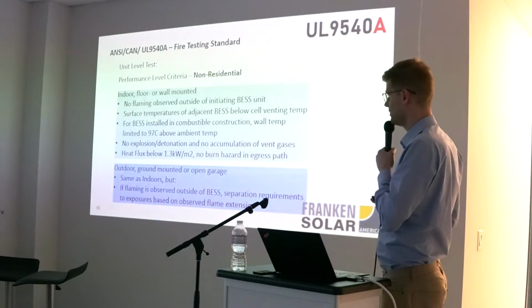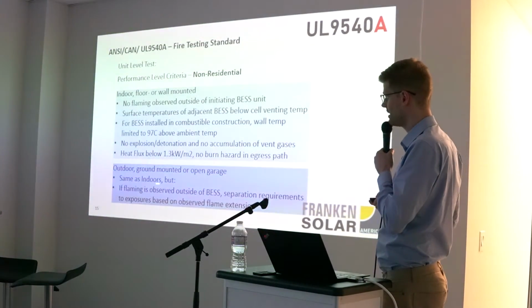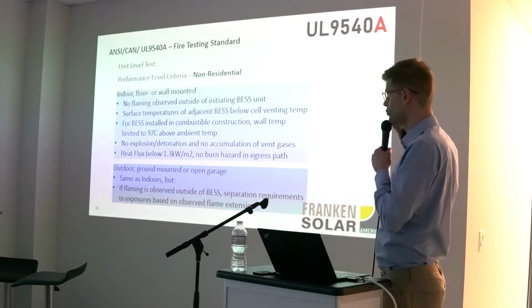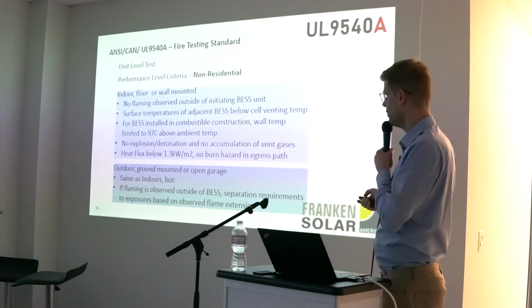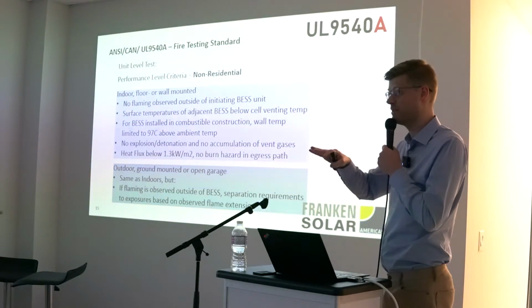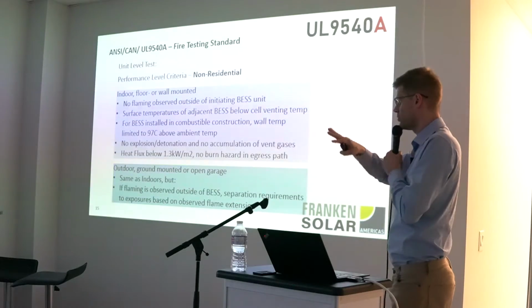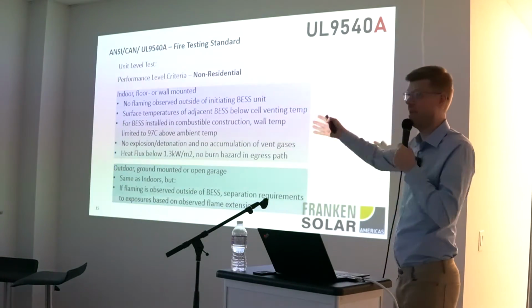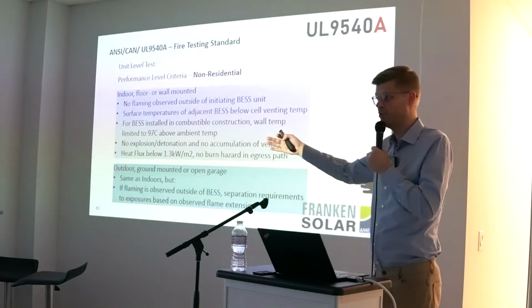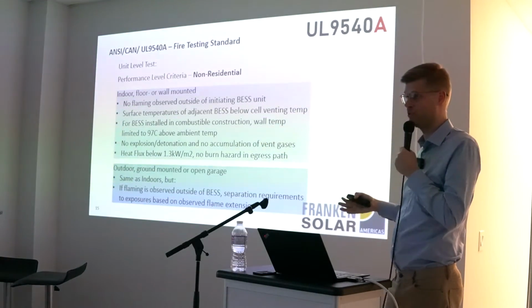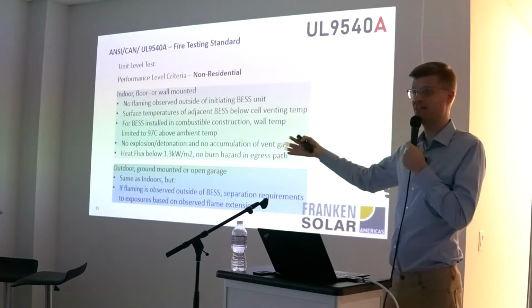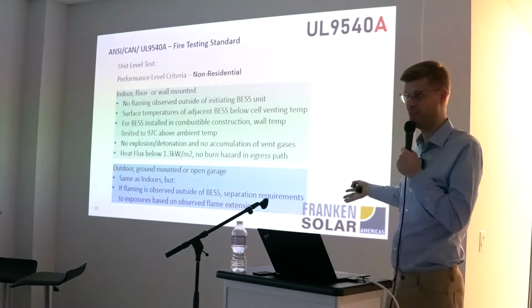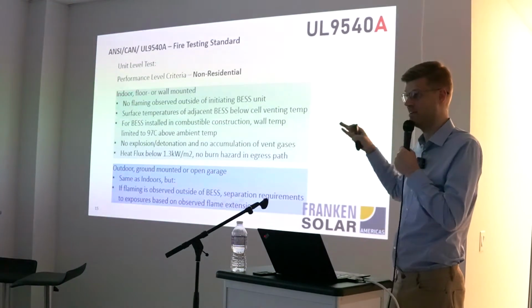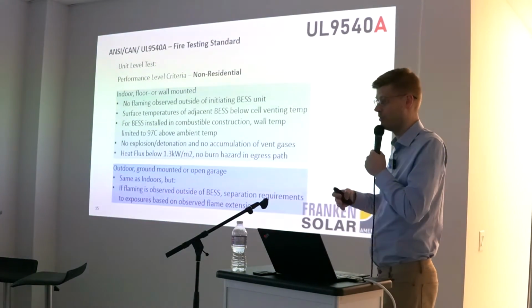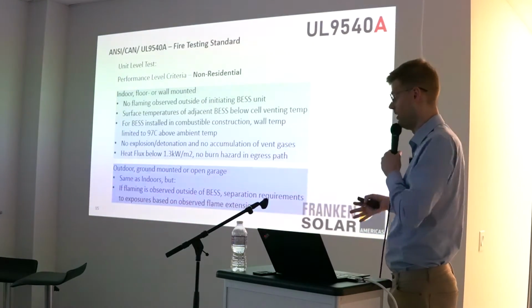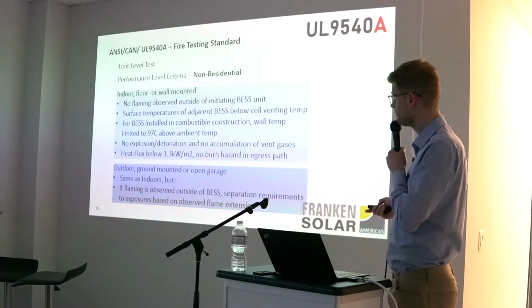For outdoor and ground mount systems, things are a little bit less strict. You have the same as indoors, but if you do have flames, then you have to have a certain separation requirement: the battery system has to be a certain distance from any other components, based on the flame length. So if flames are shooting out of the system, you can have no other equipment or building or structure within the distance where the flames are shooting out. That's pretty much the worst case example, because it's really a system that is already burning and quite badly damaged. And in order to protect life and buildings, you have to have a certain separation.